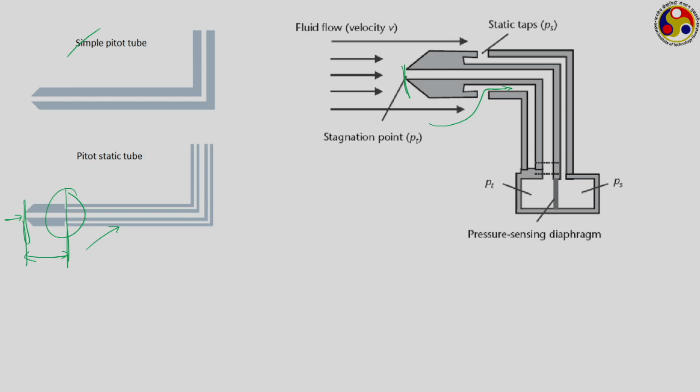So, immediately after the nose, in this position, the fluid accelerates, its velocity increases, pressure decreases. Whereas, when the stem comes into effect, the pressure will increase and velocity will start to decrease, thereby there are two opposing effects, and the position of the hole depends on how we can counterbalance these two opposing effects.